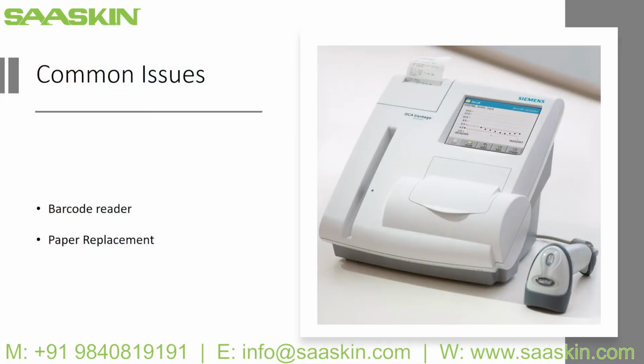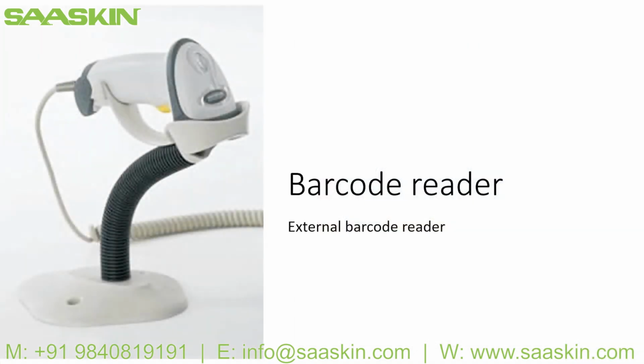Lastly, we would like to include a few instructions to address common issues that may arise during analysis. 1. Barcode cannot be read by the onboard barcode reader. The barcode reader window may be dirty and can be wiped clean using a lint-free cloth with water or ethanol. If difficulties in scanning are persistent, consider installing an external barcode reading wand which may help.